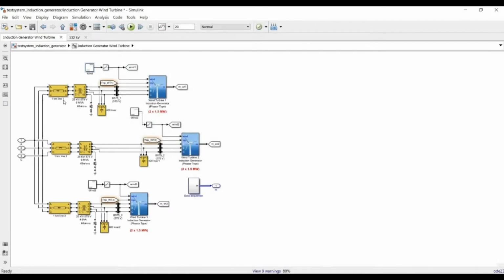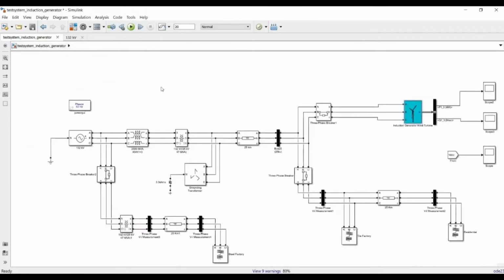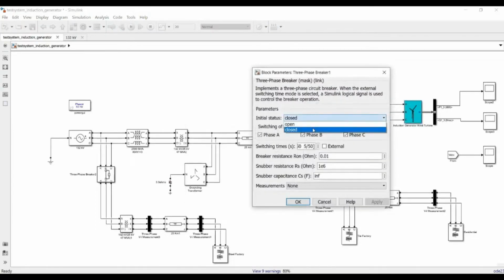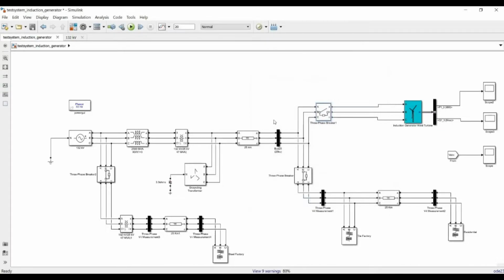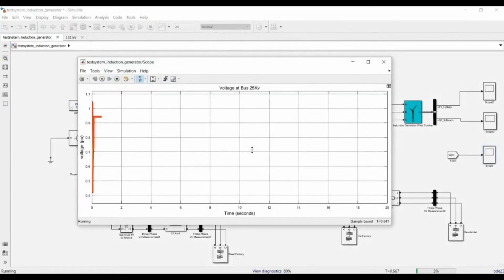First, I will run a simulation of the system before it is connected to the wind turbine. So I set it open here and I will run. As you can see here, the per unit voltage at the 25 kV bus is at level 0.94, which shows the system is a weak distribution system.